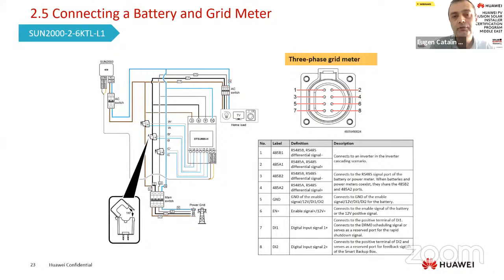Another recommendation for you is to check the meter. Do not leave the site, and do not install the meter like this. You suppose that it is correct because you respect the schematic, but you don't check the meter on the screen. The meter has an LCD screen. Normally, a meter installed correctly should measure all the power as positive. Positive for a meter means consumption.